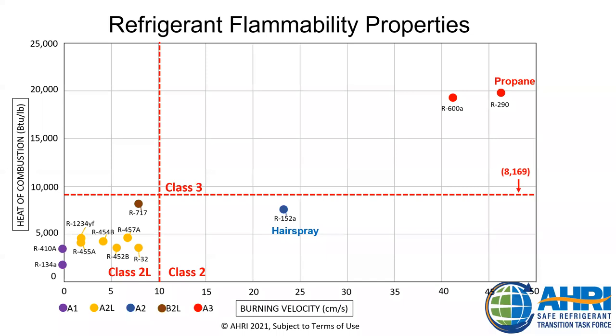I just want to show folks this refrigerant flammability property chart, which gives you a perspective of the heat of combustion, which is the energy that's released when refrigerants ignite. If I look over here, 410A, which is the common refrigerant used for air conditioning and heating applications right now, I can see that it's got some energy when it's in a fire.